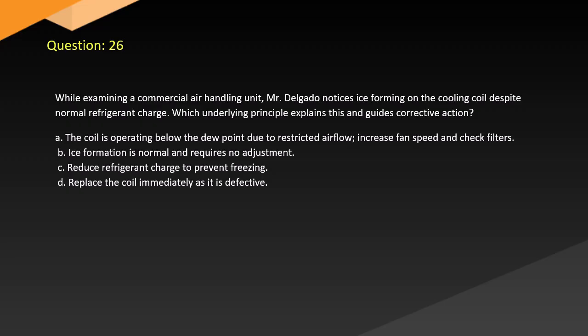Question 26. While examining a commercial air handling unit, Delgado notices ice forming on the cooling coil despite normal refrigerant charge. Which underlying principle explains this and guides corrective action? A. The coil is operating below the dew point due to restricted airflow. Increase fan speed and check filters. B. Ice formation is normal and requires no adjustment. C. Reduce refrigerant charge to prevent freezing. D. Replace the coil immediately as it is defective.